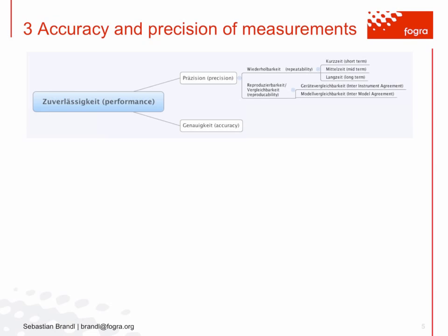The contrary to precision is accuracy, and accuracy means the difference between a reading and a given true value. While this might be the case in other physical measurements, for color measurements there is no real true value, and therefore we have traceability. There are physical standards available, reflectance primary and secondary standards. But we will see during the course of this webinar that there are practical implementations that lead to some differences which are unavoidable.